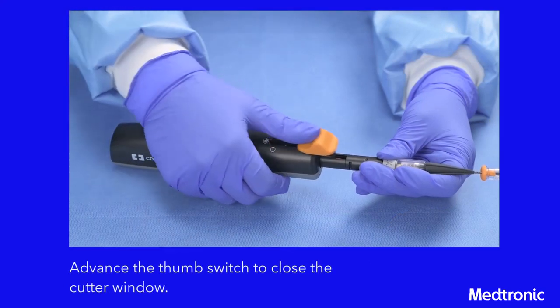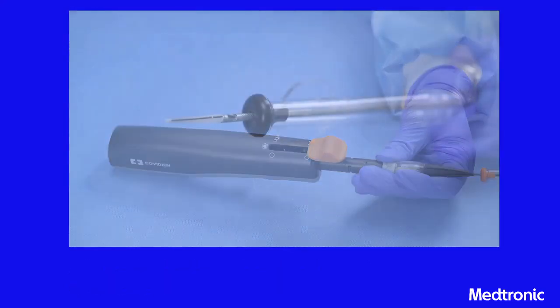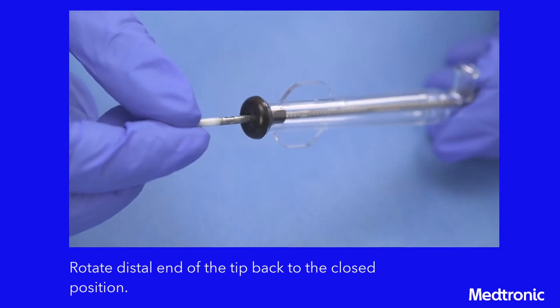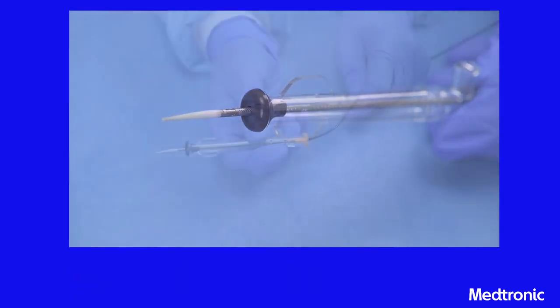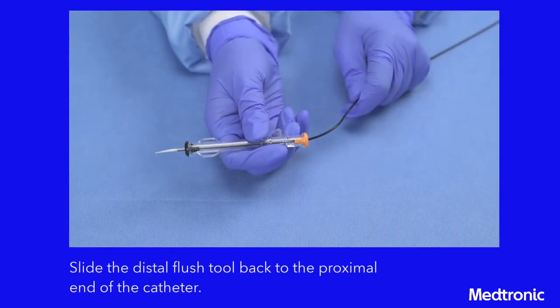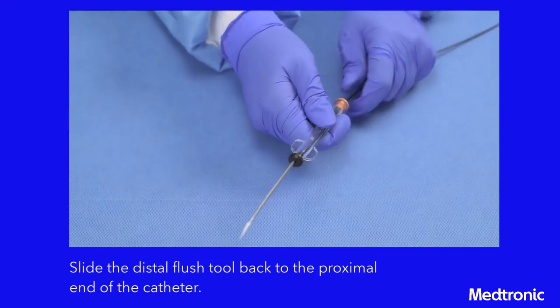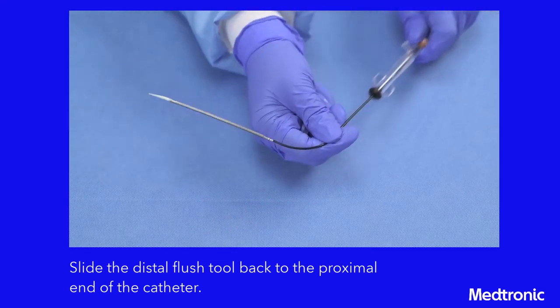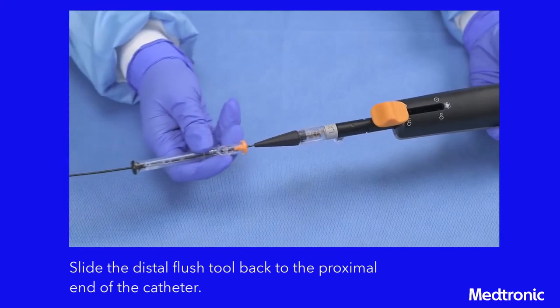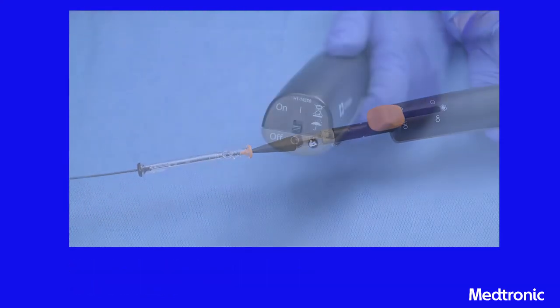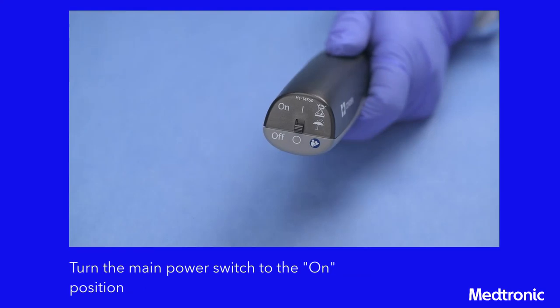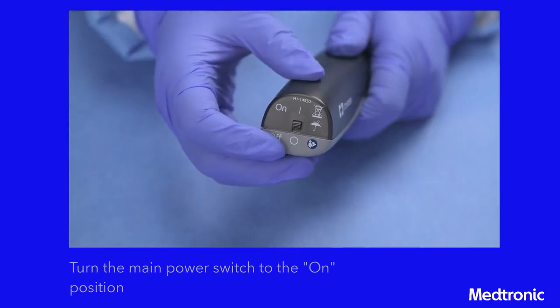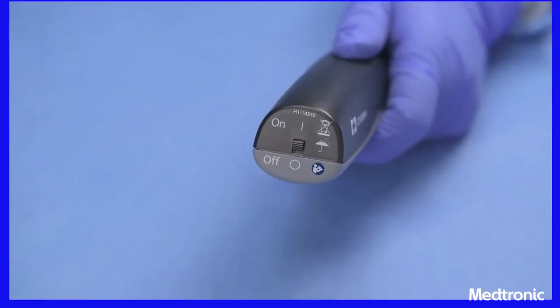Advance the thumb switch to close the cutter window. Rotate the distal end of the tip back to the closed position, and slide the distal flush tool back to the proximal end of the catheter. Turn the main power switch of the cutter driver to the on position. The catheter is now ready for insertion into the patient.